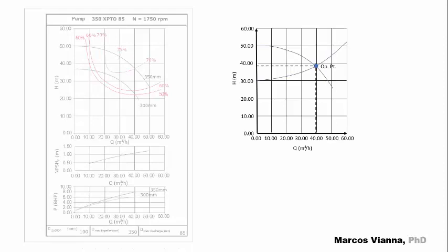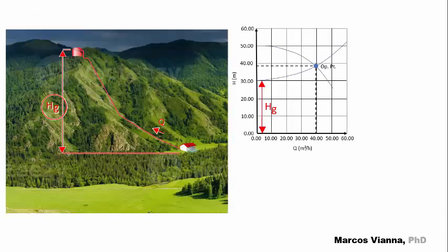Now, each system has its own characteristic curve that we must find. It begins with what we call geometric head. It's the difference between the head that we wish to reach and the initial head. The head losses corresponding to each flow in the system must be added to the geometric head.